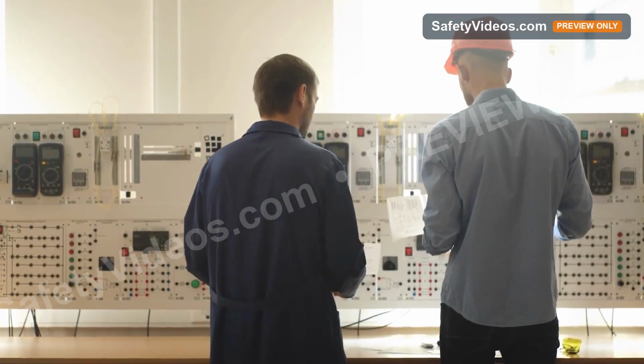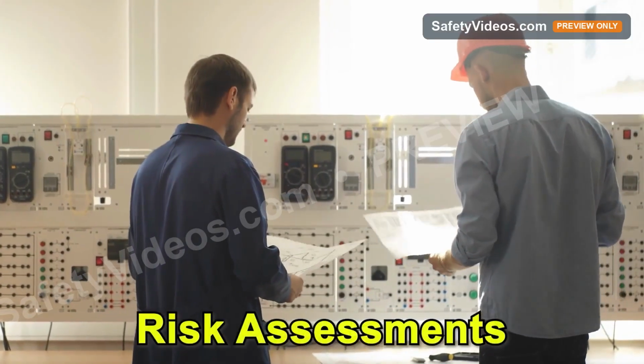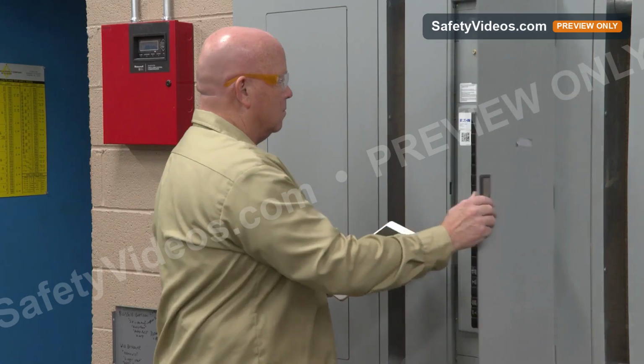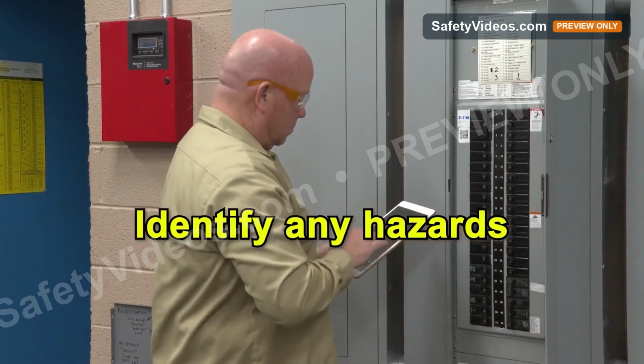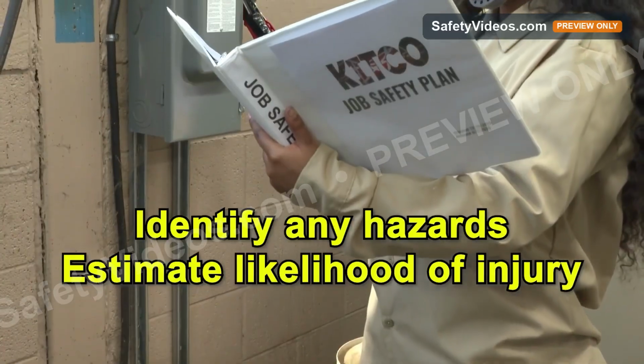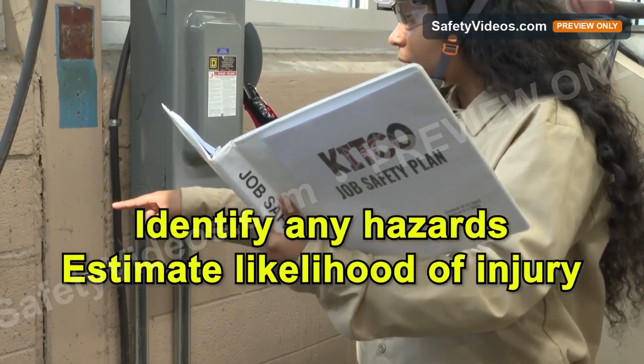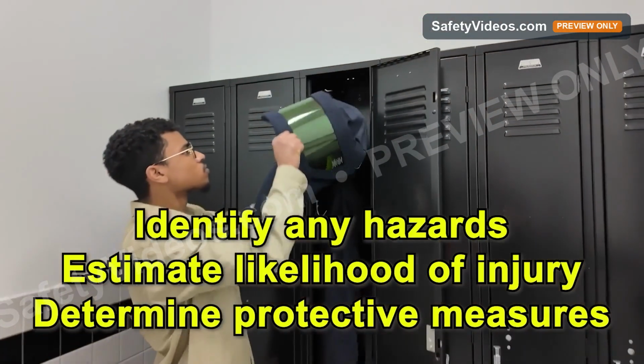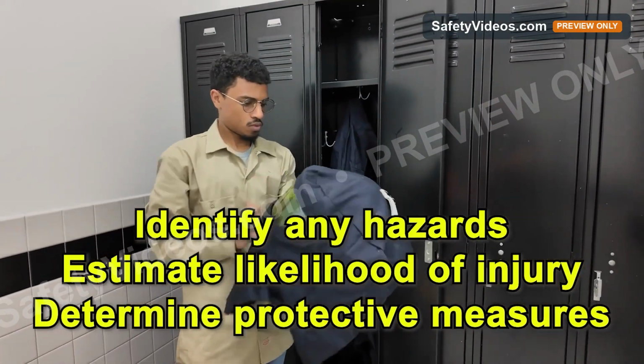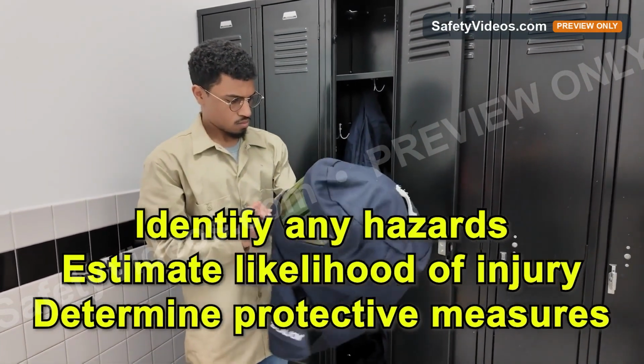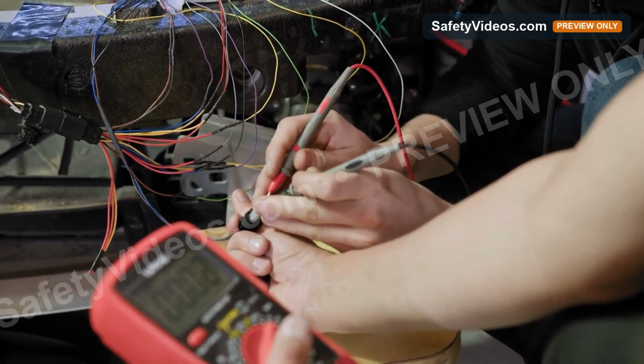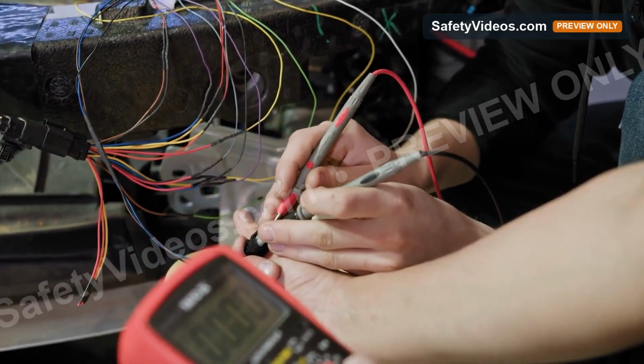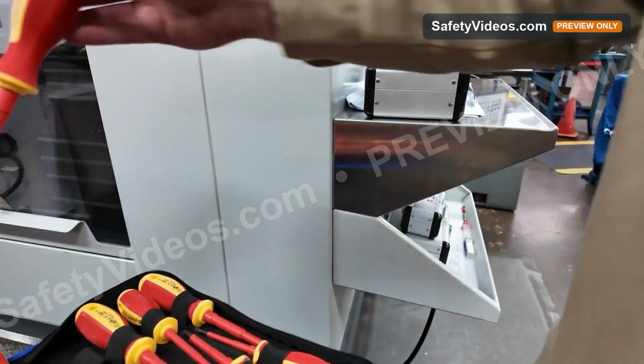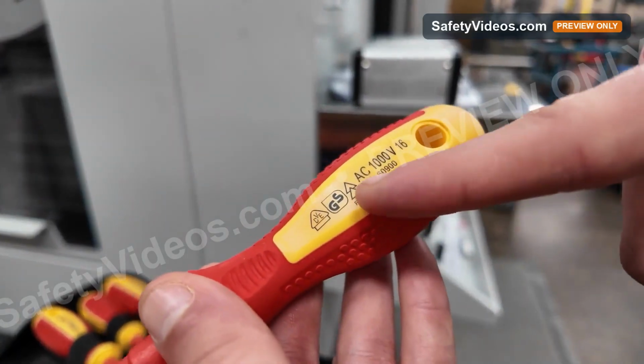When you have verified that all of your equipment is ready to use, you need to conduct risk assessments for electric shock and arc flash hazards. These assessments identify any hazards, estimate the likelihood of a potential injury or adverse health effect, and determine what protective measures are needed to complete a task safely. During the assessment, you need to determine the voltage of all the conductors in your vicinity and the voltage ratings of the tools you're going to use.